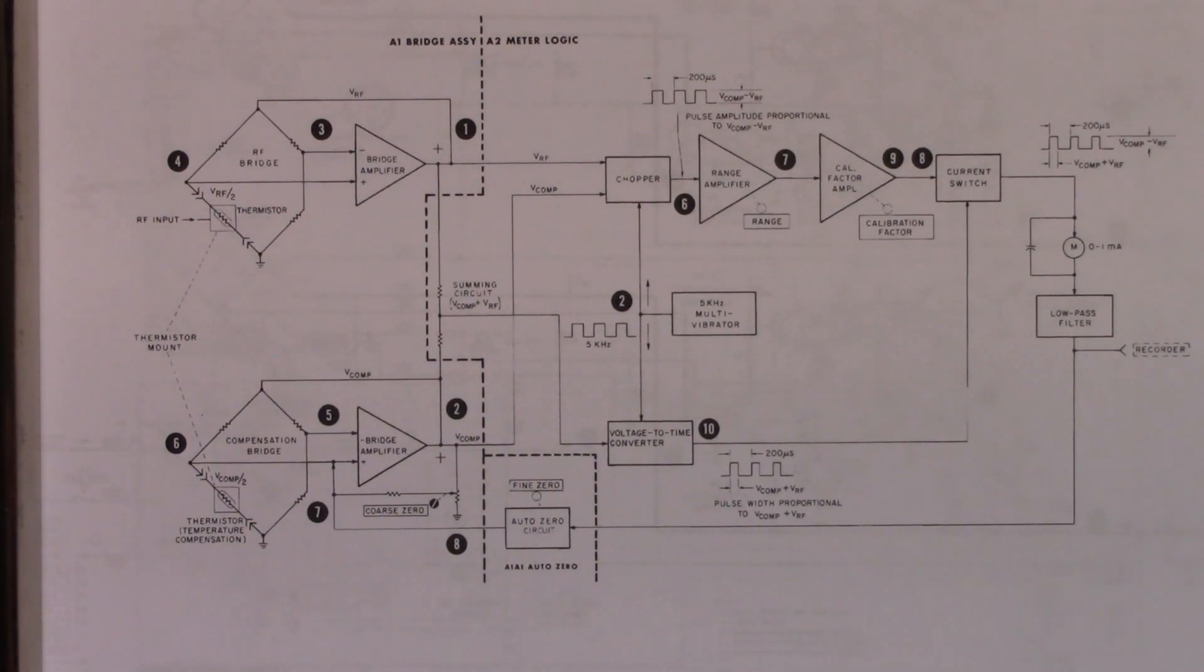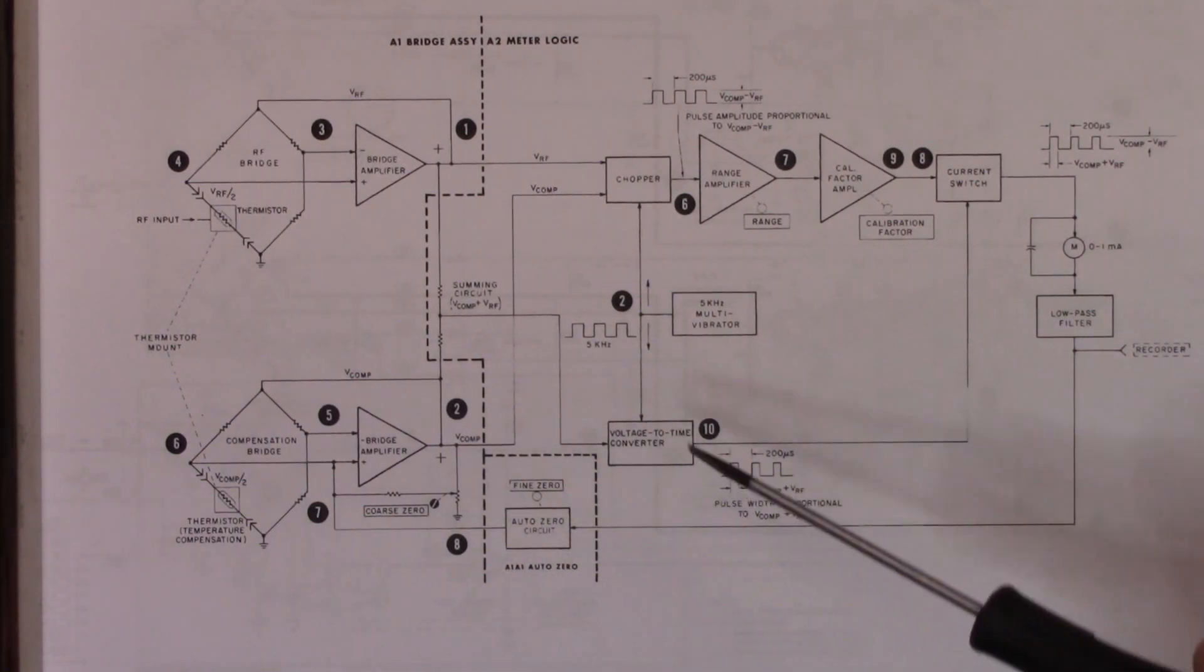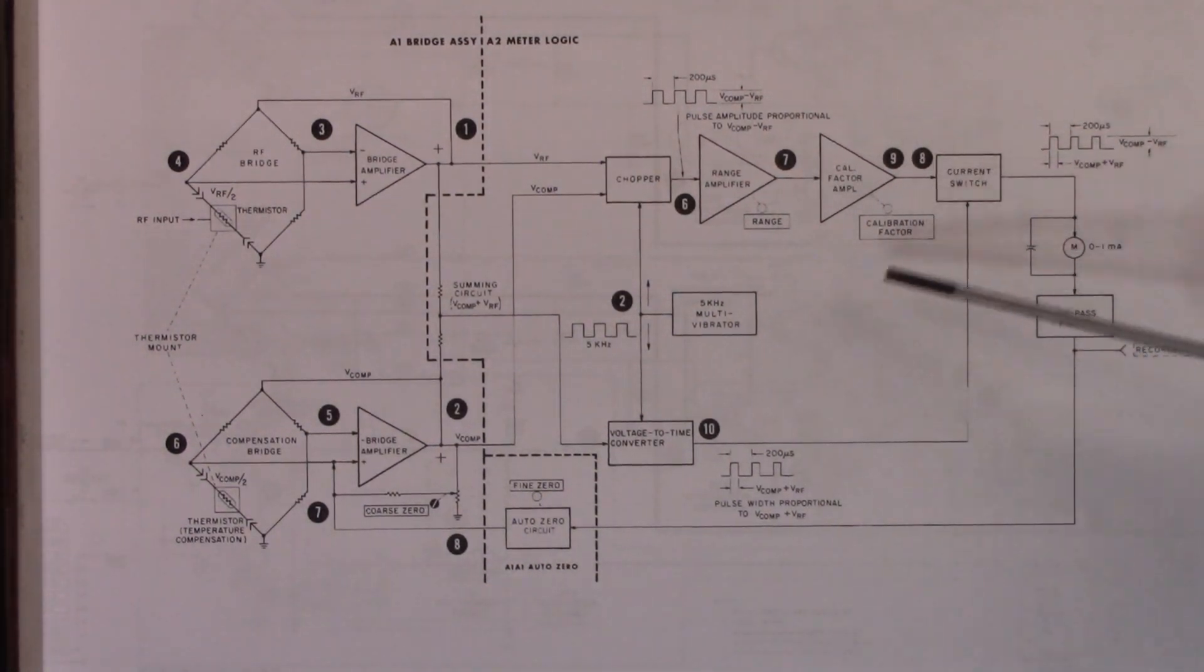Okay. Well, here is a slightly more detailed block diagram. You can see the same basic components, the RF, the compensation bridge, where they're brought together, chopped, combined, and then the resultant pulse signal filtered and presented on the meter.